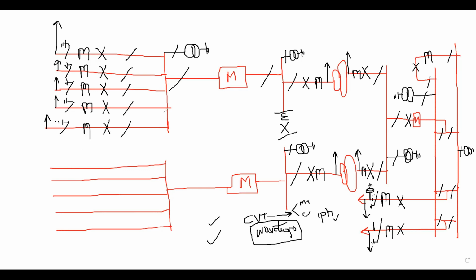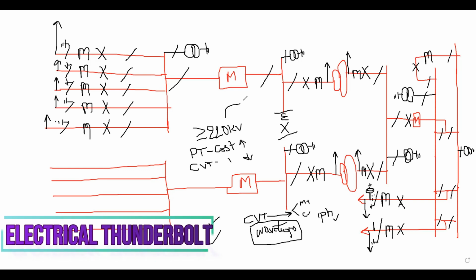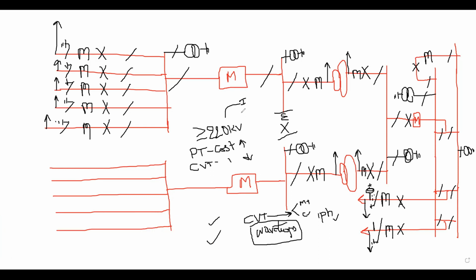But from 220 kV and above, the potential transformer cost will be high compared to the CVT. The CVT cost is less at or above 220 kV because of insulation. The voltage is related to the insulation, right? If the voltage is high, you have to give good insulation, and insulation cost will be high. So above 220 kV, instead of potential transformers, they place capacitive voltage transformers only.